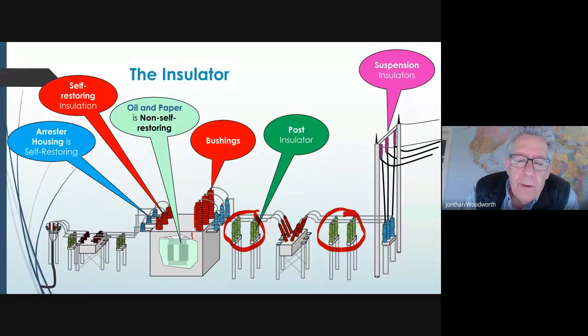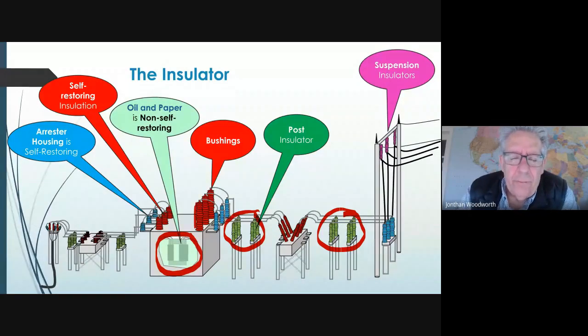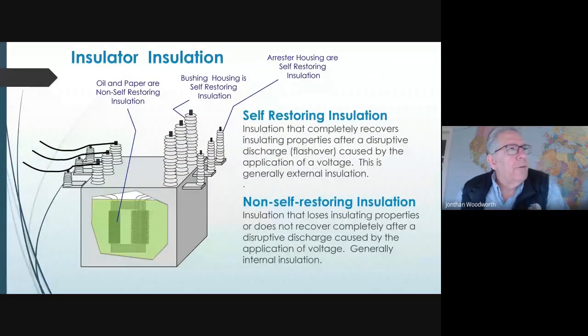be protected. In a substation, the windings that are under the oil inside the transformer are absolutely the primary target for surge protection. Because this is called non-restoring insulation or non-self-restoring insulation, the industry spends a great deal of money putting arresters on all around transformers to make sure that the voltages never get too high. So in the substation and outside the substation, the primary purpose of surge protection is to keep the insulators from flashing over. And I'll show you in a couple slides what I'm talking about.